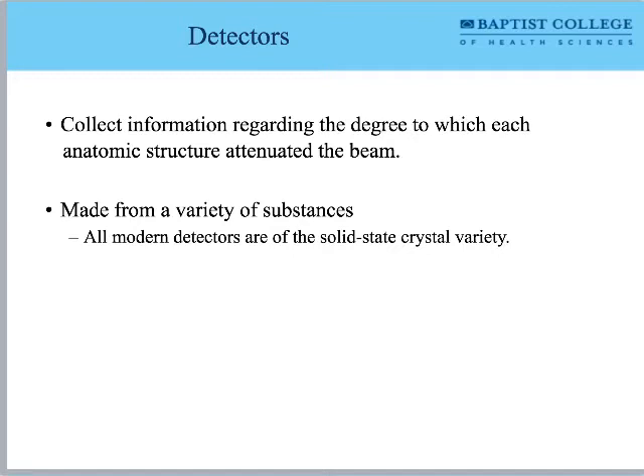Detectors collect information about the degree to which each anatomic structure attenuates the beam — they're capturing the remnant beam, detecting both the original and remaining signal. This is why in nuclear medicine we can use CT for attenuation correction. Detectors are generally made of some kind of solid-state crystal. Back in the good old days they used xenon gas, but pretty much no one uses that anymore — almost everything now is solid-state crystal.